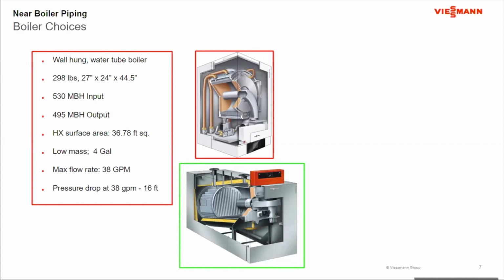So, a wall-hung water tube boiler. Okay, and as a wall-hung boiler, one of the key design words is compact. It has to be compact. So this boiler here at 530,000 BTU input is 298 pounds. Size-wise, it's 27 by 24 and 44.5 inches tall. It has a heat exchanger surface area of 36.78 square feet. It's low mass. It holds 4 gallons of water.